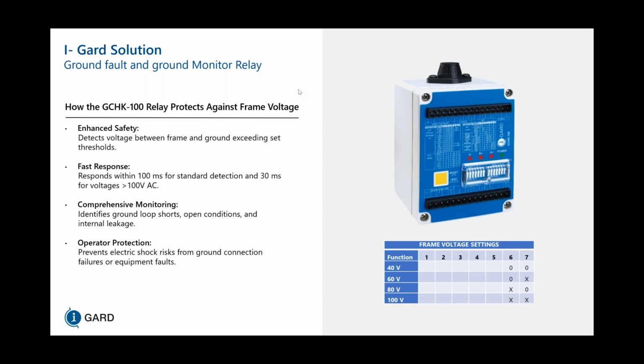Where does the output of the relay get wired to shut down equipment or isolate electrical equipment? So, Sanjay, the relay has dry contact outputs that can be wet with a voltage of 120 volts AC, and then they're normally open in normal operation and will close when a fault is detected to trip the breaker that is connected to those dry contacts. Can the relay communicate to other control systems such as DCS?